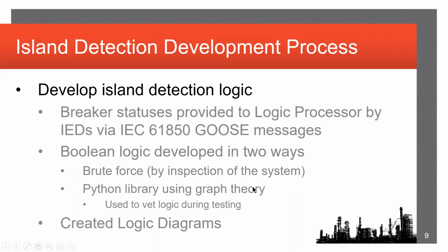So after the functional specification was developed, the next major task was to actually develop the Boolean logic to make that determination. As I said, there are various IEDs throughout the system connected to all of the pertinent circuit breakers that we wanted to monitor. Those IEDs would then send that status via IEC 61850 GOOSE messaging back to the central logic processor.